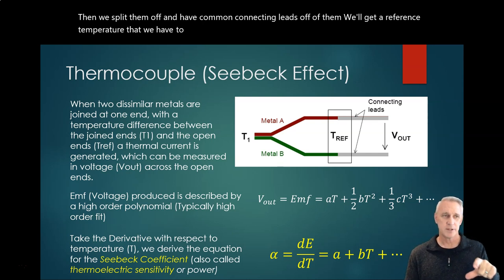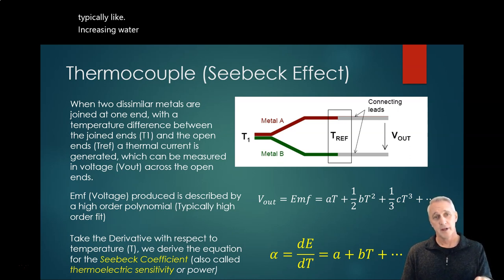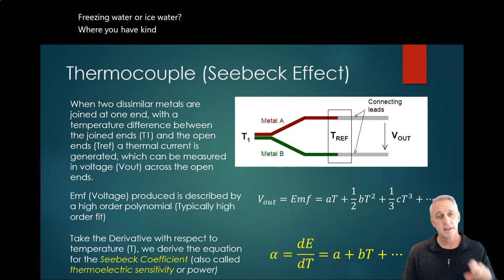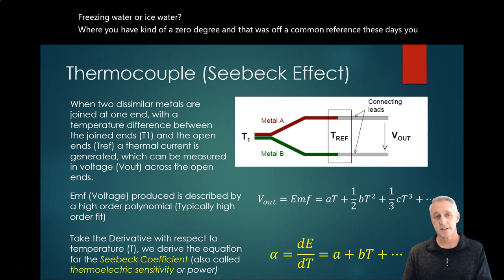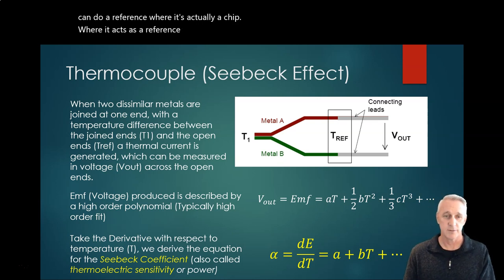It used to be that we used a reference temperature typically like freezing water or ice water where you have kind of a zero degree common reference. These days you can do a reference where it's actually a chip where it acts as a reference electronically so you can get the relative difference, and then you can measure the voltage out.